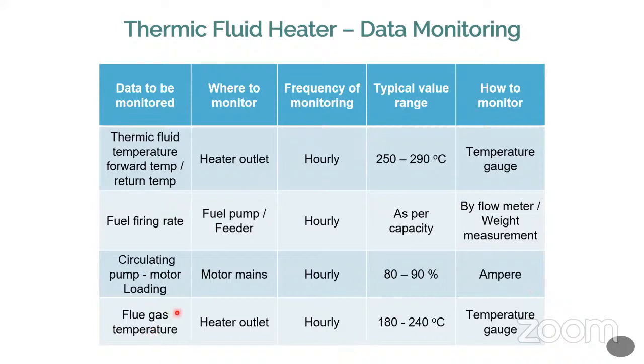Then we have flue gas also available, because it's a burning process. So there must be flue gas available, and that should also be monitored at the outlet of the system. Again, that should be monitored at least 3 times in a shift or 3 times a day. The temperature should be within the limit of 180 to 240 degrees. More than that, automatically more heat will be taken by the flue gas. If it is lesser, it means not proper firing, not proper combustion. This is the indication of your flue gas.